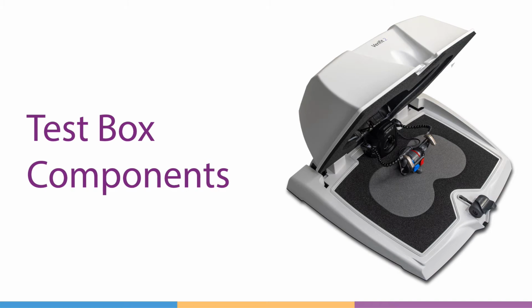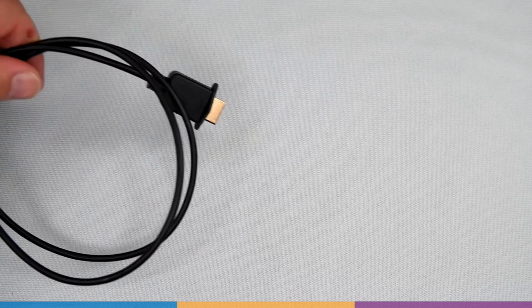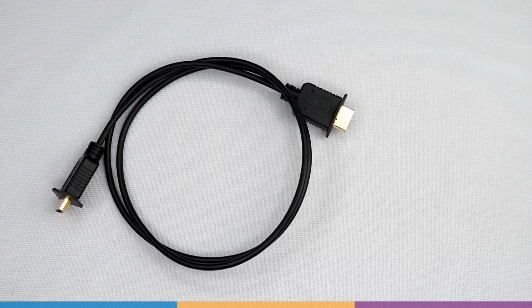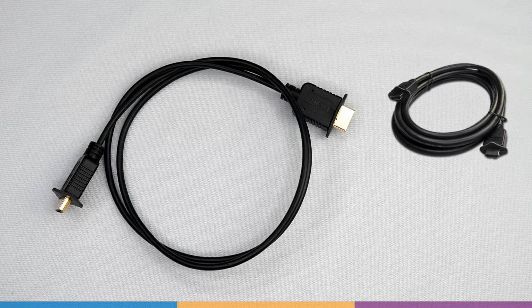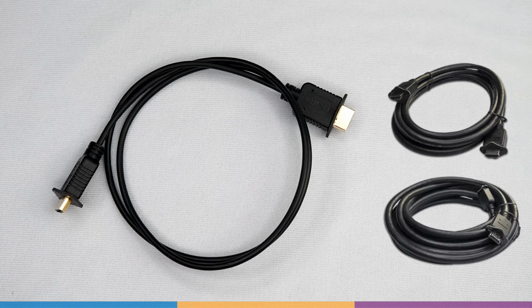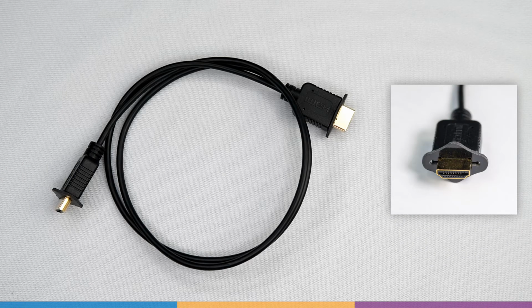Test box components. The test box cable connects the test box to the display unit. The standard length included is 1 meter or 3 feet, which allows for easy side-by-side positioning. For different setups, longer cables are available from your Audioscan distributor. The test box cable uses HDMI connectors, however it does not carry an HDMI signal, so it is important not to attempt to use off-the-shelf HDMI cables.